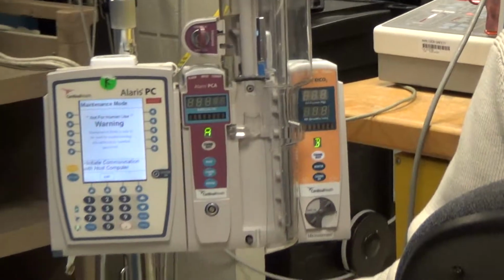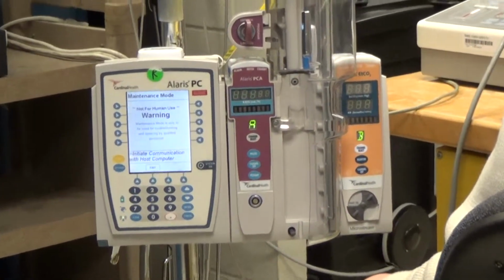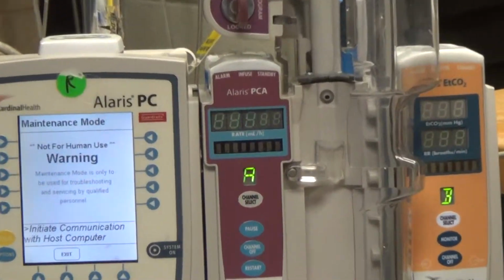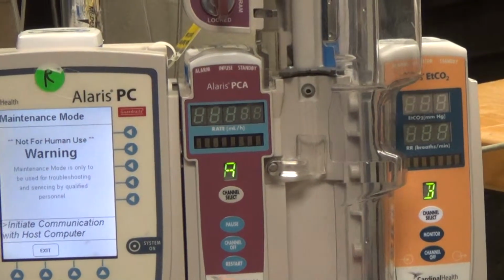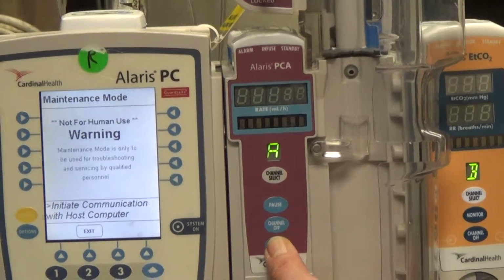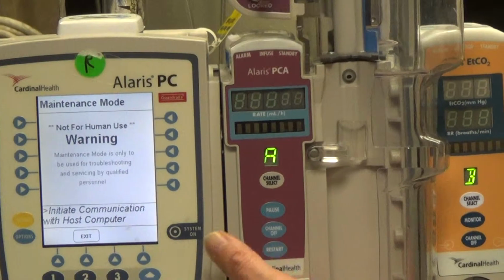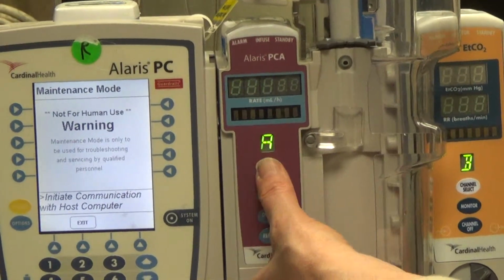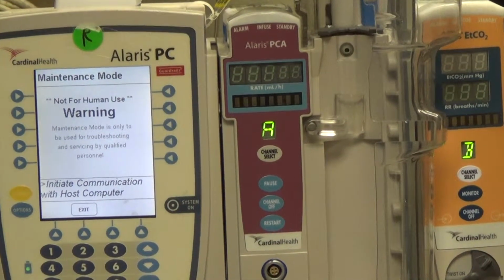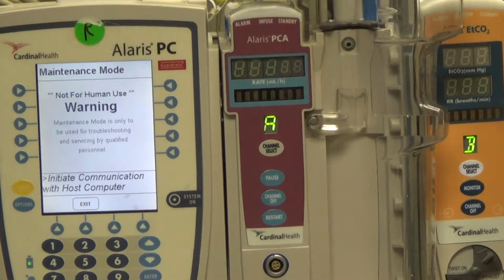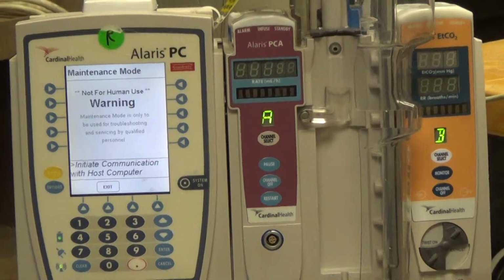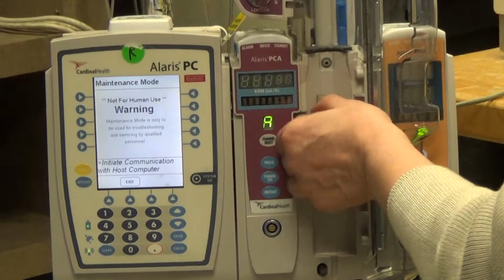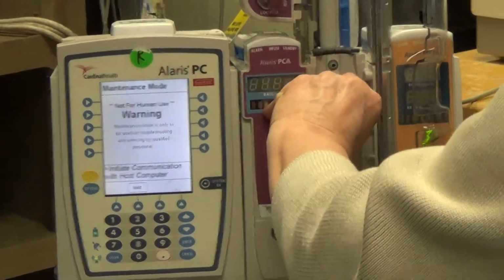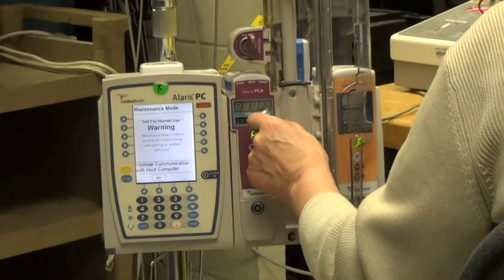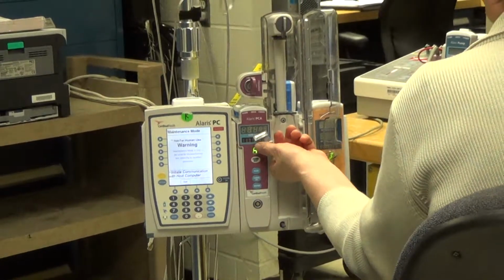Here you hear the alarm and you see the alarm. On the next page, we check that these push buttons work: the restart, channel off, the pause, and the channel select. Everything works correctly, so we move on. Here we check again our barrel clamp to test and to go on.